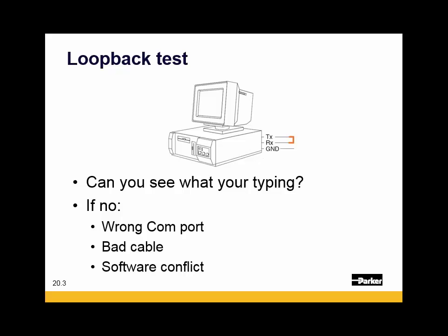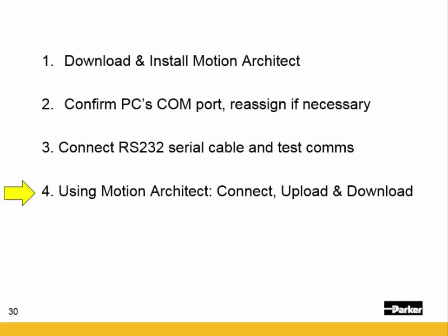If you still can't get a loopback, the other thing that could be going on is a bad cable. So try a different cable. Again, it's just pins 2, 3, and 5. If you can't get a loopback to work, then you could have a short to ground, or it could be open, or a bad solder joint on there.